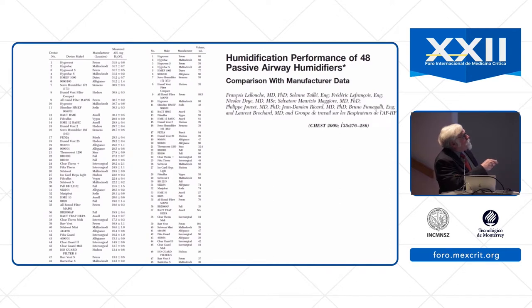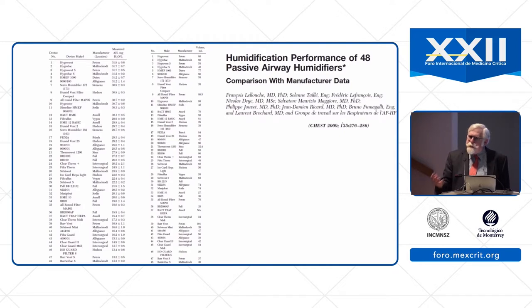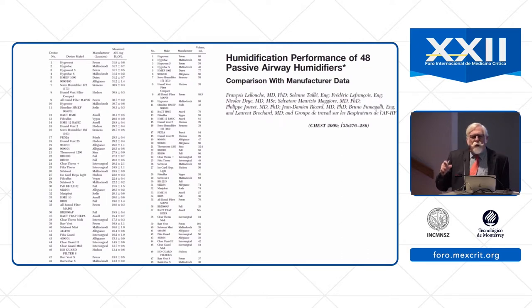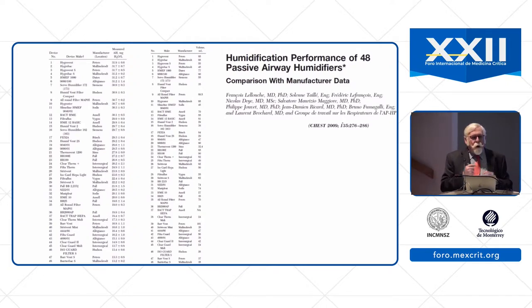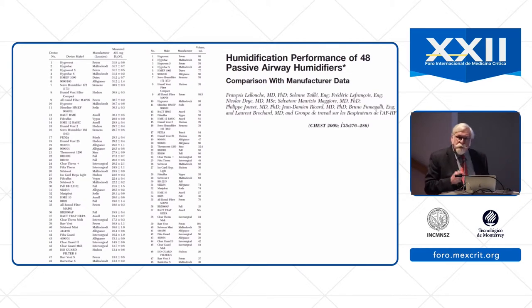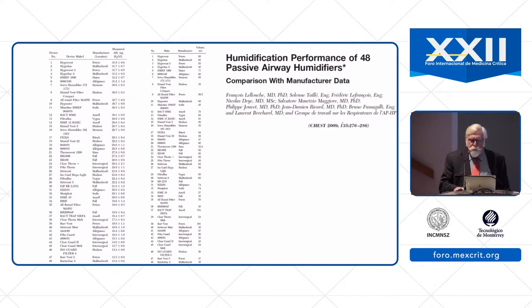They also found a big difference among devices in dead space volume. Some devices had a dead space volume as low as about 30 milliliters, whereas other devices had a dead space volume as high as 100 milliliters. Not all of the dozens of commercially available devices are equivalent. You need to know whether the device you are using in your practice is a good or a poorly performing one.